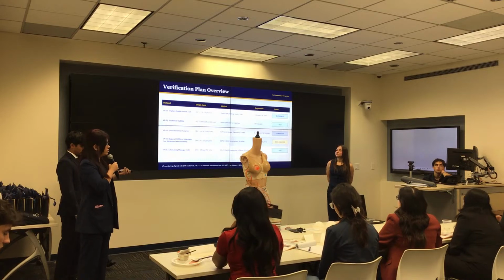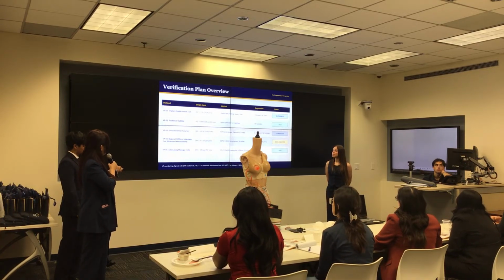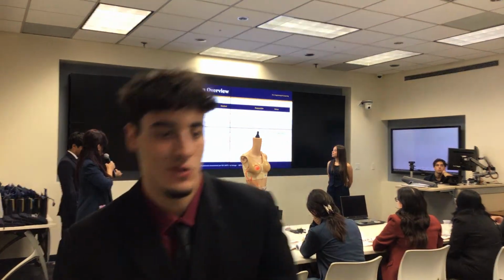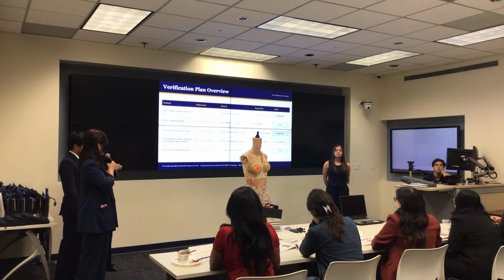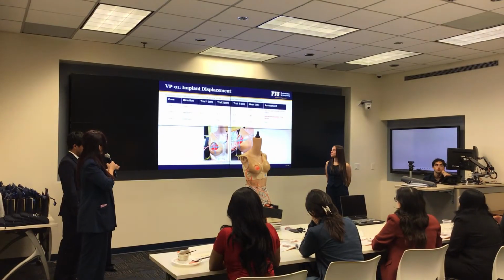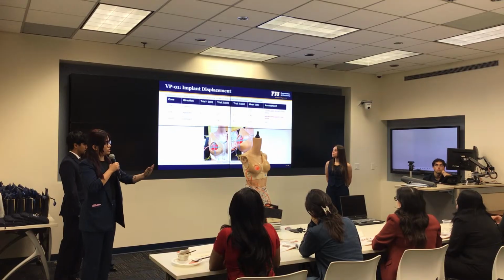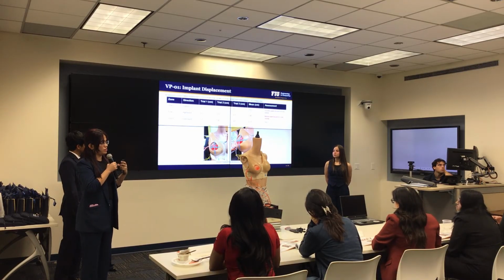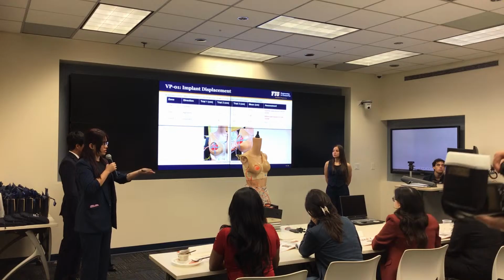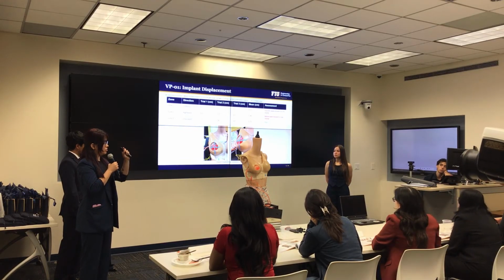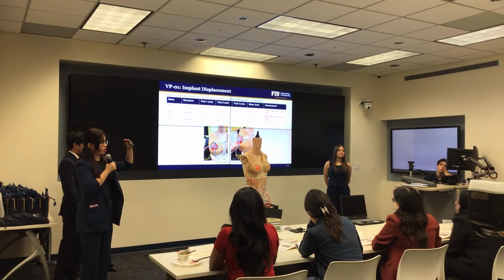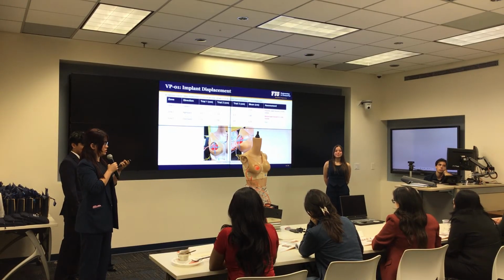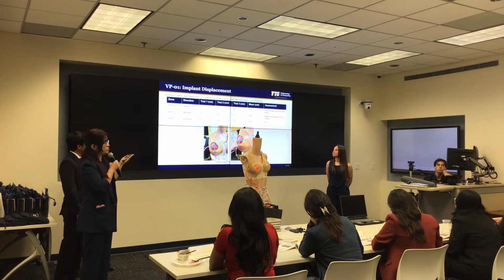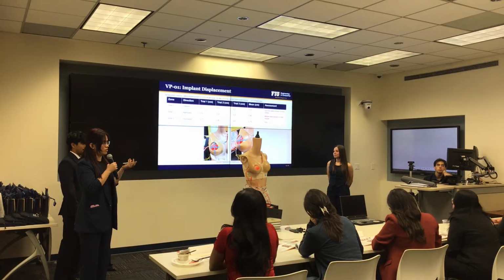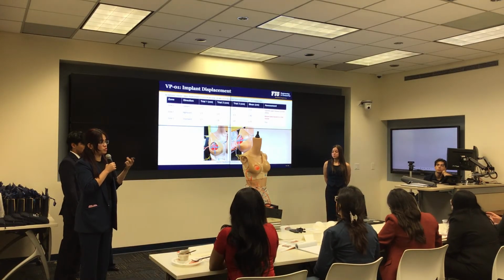So we have the protocol: VP1, implant displacement test; VP2, positional stability; VP3, pressure sensor accuracy; VP4, regional stability indication, and the alternative massage cycle. So for BP1, we put a tape across, and we put an implant inside the bag with some fluid so it can displace. And we turn on the machine, and we check, put a dot in the middle, and we check how much it displaces up and down, and we measure it with a standard. We went and met a doctor, and he told us how much it should displace in the massage.